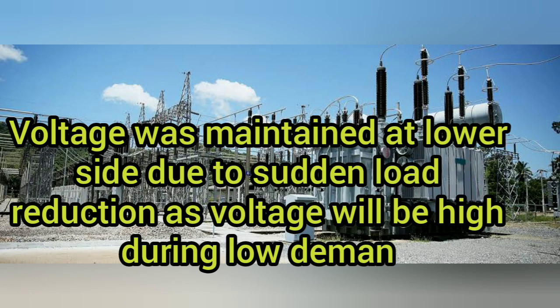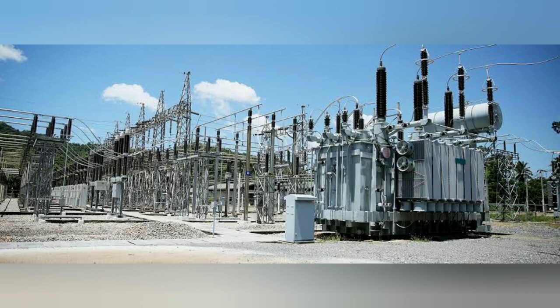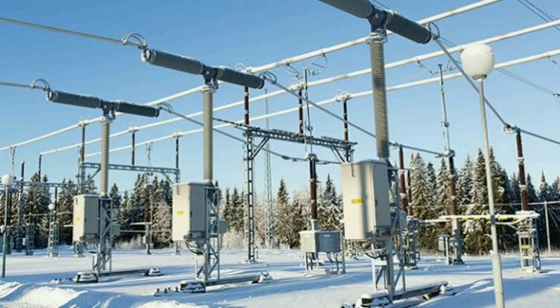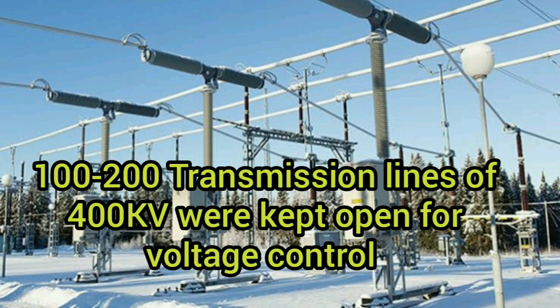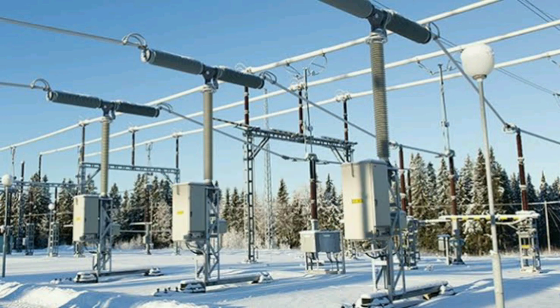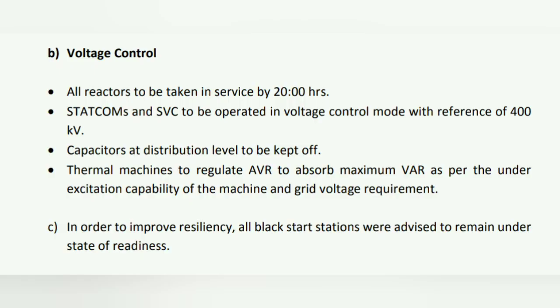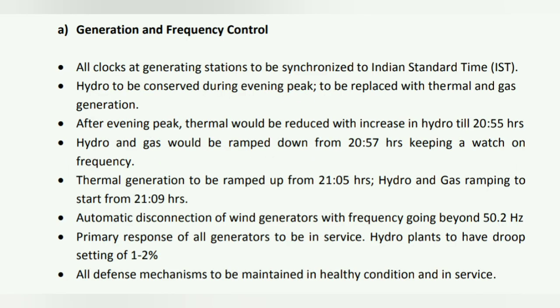Further, in order to avoid high voltage at the time of sudden reduction in demand, the voltage prior to the event was maintained on the lower side. A total of 100 to 200 transmission lines of voltage level 400 kV and above, that is HVAC and HVDC, were kept open for voltage control. And switchable line reactors and bus reactors were taken in service wherever required. SVCs at 400 kV were taken in voltage control mode with reference voltage of 400 kV. STATCOM settings were modified as per requirement.